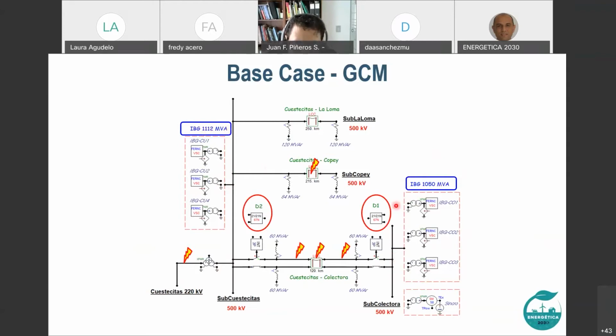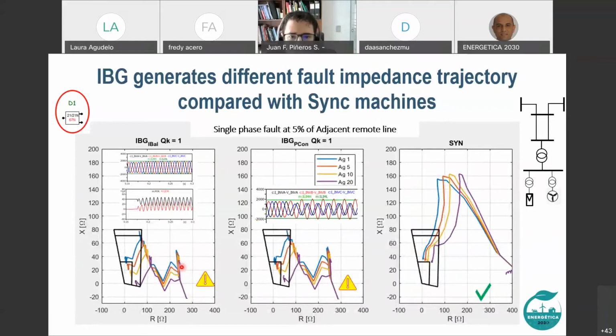We are now focused on analyzing the performance of these distance protection relays here in D1. I will refer to it as D1 all the time. We were simulating internal faults in the lines these relays are protecting, and as well some external faults here in the external adjacent line, Cuestecitas Copey. We were also simulating faults at the other voltage level, at substation Cuestecitas 220. Okay, let's see what our findings are.